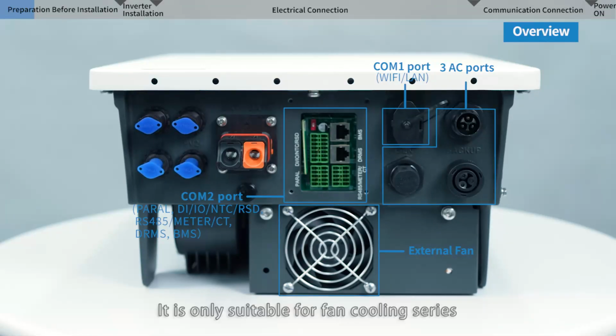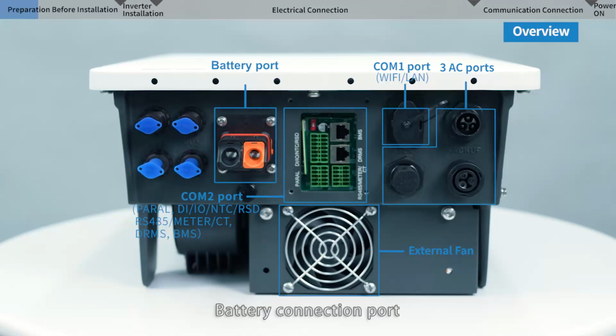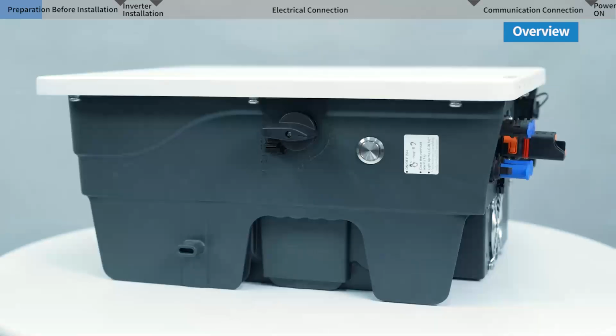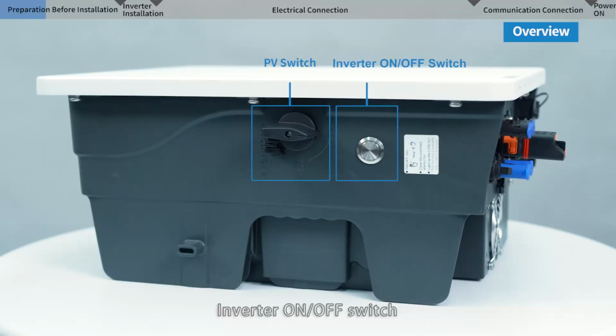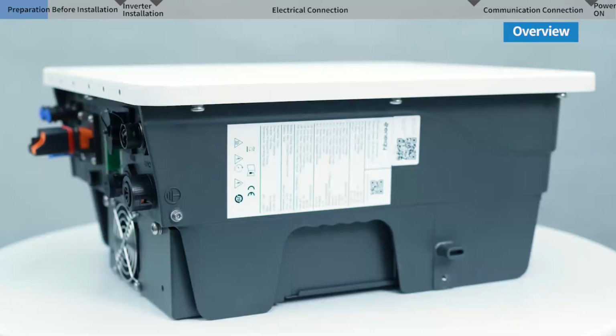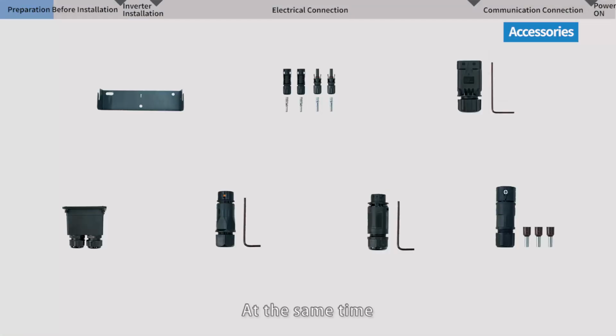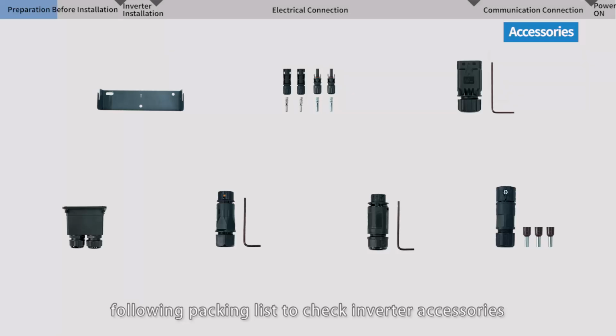External fan. It is only suitable for the fan cooling series. Battery connection port for battery cables. PV connection ports. On the left side, we can find the PV switch and the inverter on-off switch. On the right side, we can find the grounding terminal to install the grounding cable. At the same time, follow the packing list to check the inverter accessories.